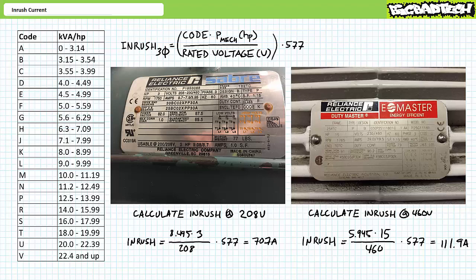Motors with a kilovolt ampere per horsepower constant at the upper end of the alphabet nearer to A exhibit less inrush than a similarly rated motor with a constant in the lower depths of the alphabet nearest to V. Additionally, these examples illustrated that inrush, although brief, can put a tremendous strain on the electrical distribution system that must be anticipated in advance.